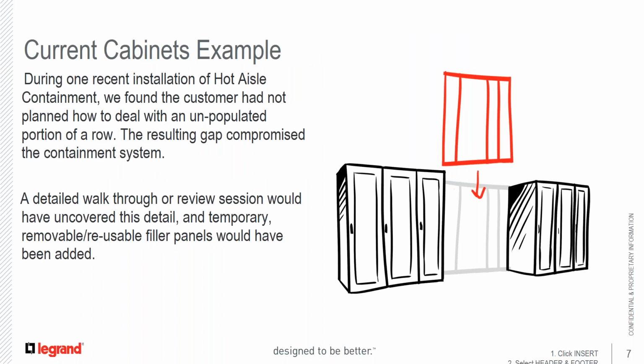Here's an example. During one recent installation of hot aisle containment, which is the most prevalent approach to containment in new construction data centers, we found the customer had not planned for an unpopulated portion of the row. This resulted in a gap in that aisle, which totally compromised the functionality and efficiency of the containment system. So please plan in advance.